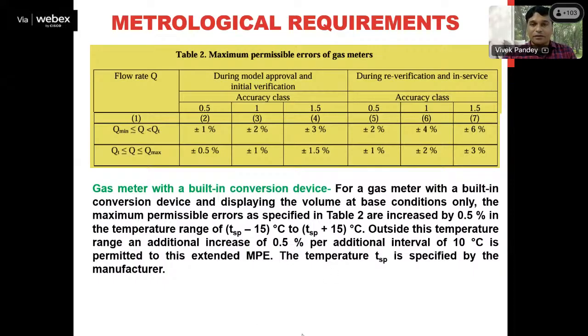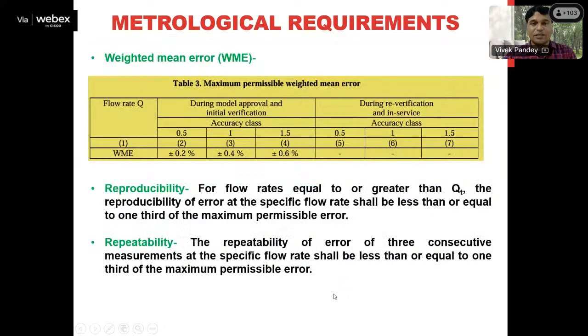So this is about the MPE or the tolerance during the accuracy test. Now this is the table specified for the weighted mean error. I just spoke about this parameter. In the case of weighted mean error, I told you that this is a very important parameter basically. Why? Because it can tell you directly whether a gas meter is working fine for all the flow rates specified or not, within minimum to maximum flow rate, because it is a weighted quantity. It is the effective quantity for all the flow rates, fine. And this particular parameter is mostly used for a gas meter during pattern approval, sorry, model approval and initial verification, fine.